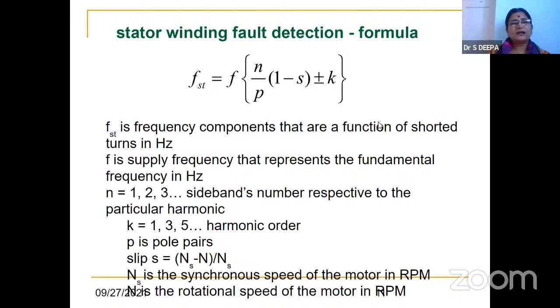In the literature, they say that if this type of fault is there, these frequencies will shoot up. Normally our supply frequency is 50 hertz. Harmonics are multiples, integer multiples, of the fundamental. Mostly odd harmonics will be shooting up; even harmonics will not be there. So here Fst is the frequency component that is a function of shorted turns, in hertz. Whenever I have a stator fault, it depends on these parameters. F is the supply frequency that represents the fundamental in hertz, n is 1, 2, 3, the sideband number for the particular harmonic, k is the 1, 2, 3 harmonic order, and p is the pole pairs.